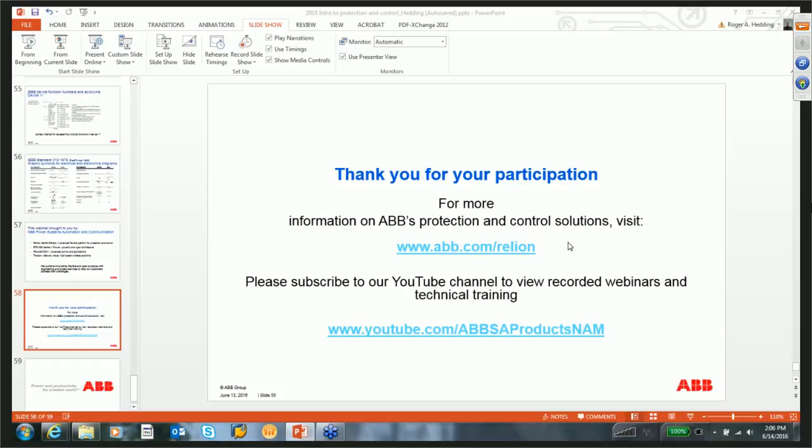What is an NCIT sensor? An NCIT sensor is a non-conventional instrument transformer, and that could be using a Pockels cell for a voltage sensor. It could be using a fiber optic CT for a current sensor. It could be a Rogowski coil. Anything that doesn't use the conventional electromagnetic circuit for the current and voltage is a non-conventional instrument transformer. And now those devices can actually be streamed with the IEC 61850 information into the relay without having to go through any kind of A to D converter anymore.